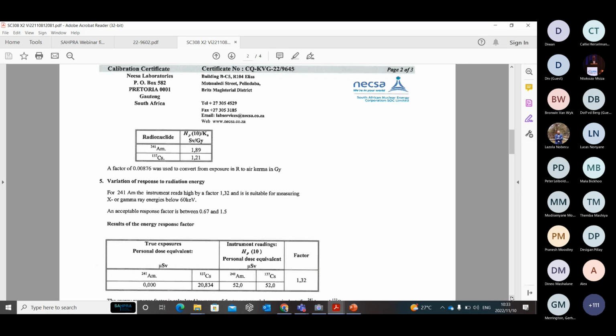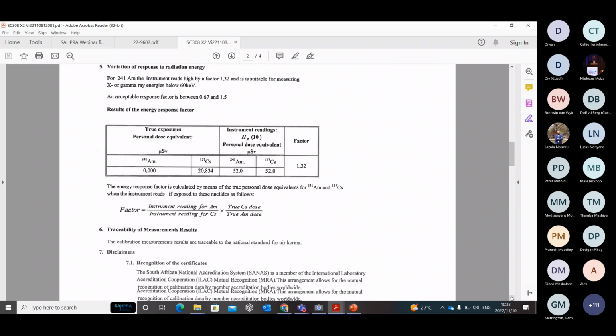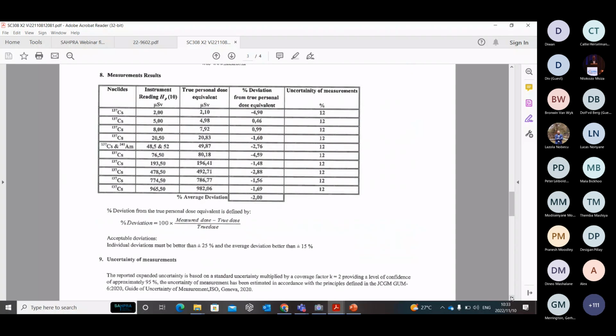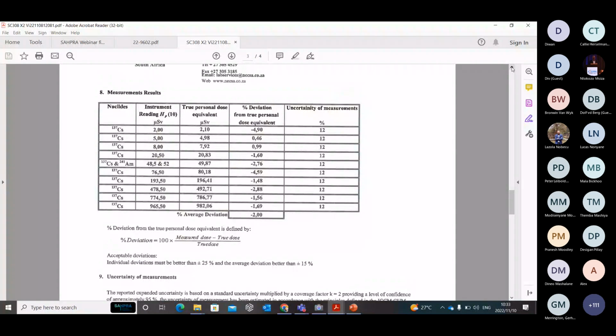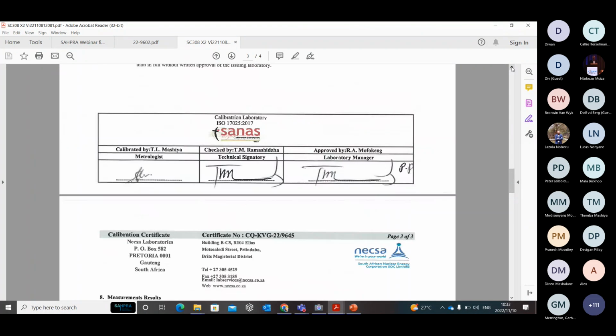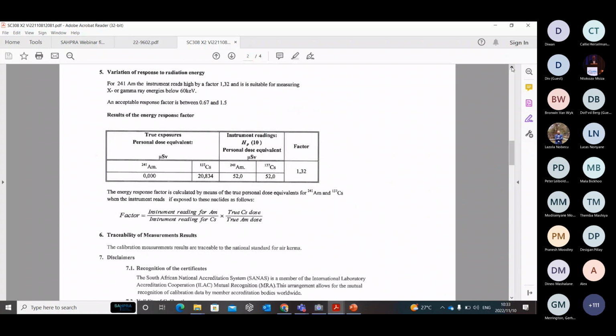And then let me see the table below. Go up a bit. Okay, thank you. This is the table where you determine your energy response factor, and a good energy response factor should be within this limit. This is the formula: instrument readings for americium divided by the instrument readings for cesium, multiplied by the true dose for cesium and divided by the true dose of americium. It gives us this value.